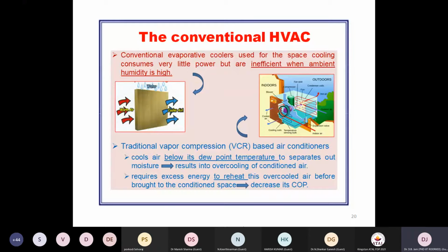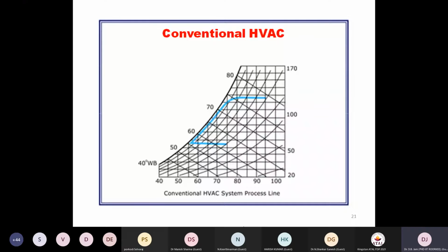What is the way the conventional HVAC can remove the humidity and temperature? This is a tool or chart called the psychrometric chart. As you see here, the blue lines represent first cooling the air sensibly, and then at the saturation condition, humidity in the air is partially condensed and removed in the form of water to make the air dry and reduce its humidity. At a further stage, the same air is reheated if overcooling occurs.